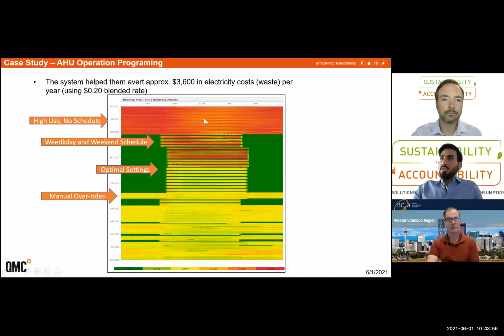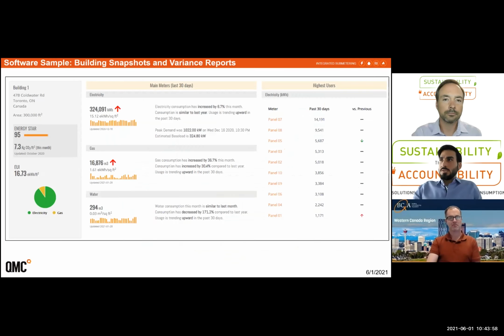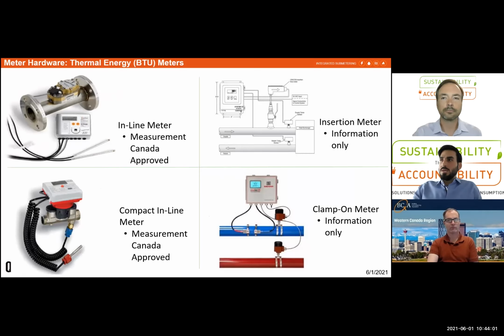Sure. So inline meters, with larger inline meters, it would be highly dependent on the pipe size and the size of the meter. And these meters would cost anywhere from 1 inch, ranging from $600-700 and going all the way up to 20-inch and 24-inch lines in and around $20,000 to $25,000. The compact meters, depending on whether they're revenue grade and approved and where they're made, range anywhere between $200 to $250 to about $500 to $550.